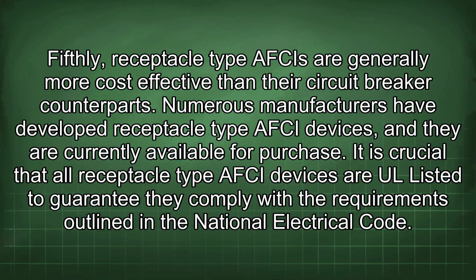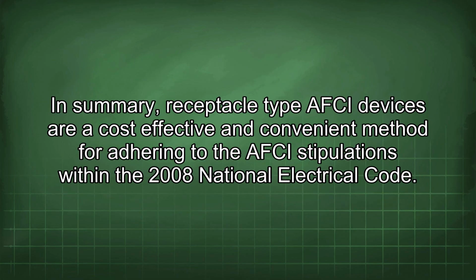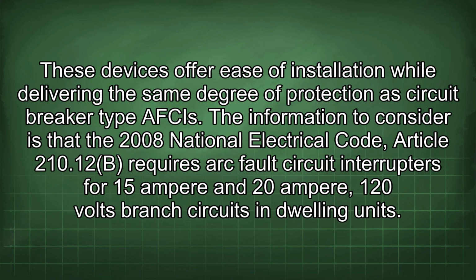Numerous manufacturers have developed receptacle type AFCI devices, and they are currently available for purchase. It is crucial that all receptacle type AFCI devices are UL listed to guarantee they comply with the requirements outlined in the National Electrical Code. In summary, receptacle type AFCI devices are a cost-effective and convenient method for adhering to the AFCI stipulations within the 2008 National Electrical Code.